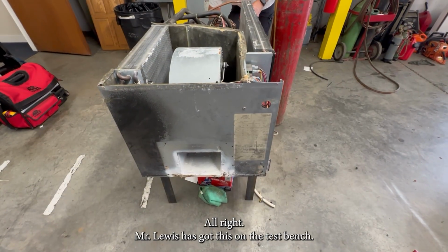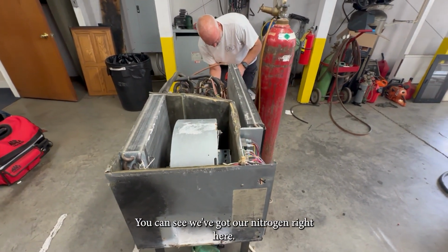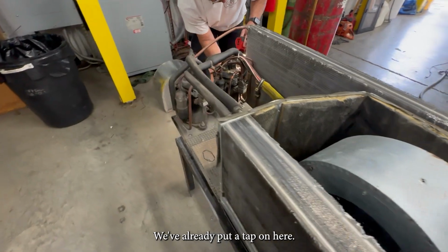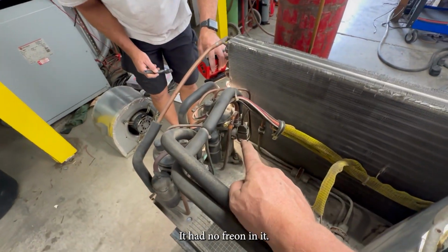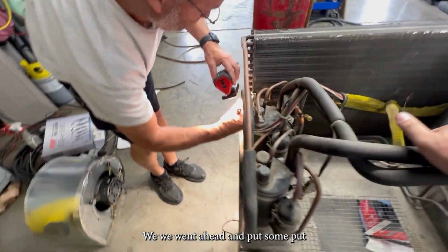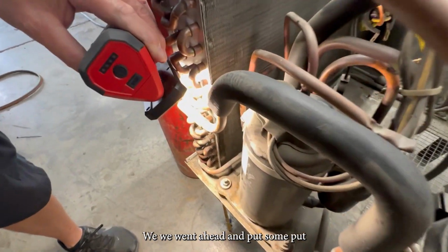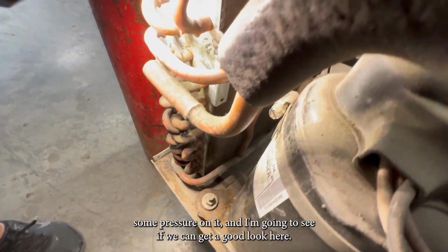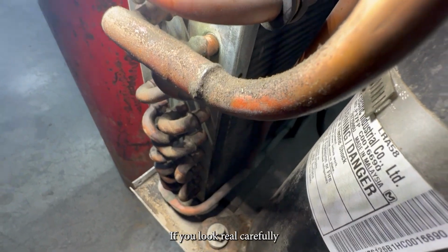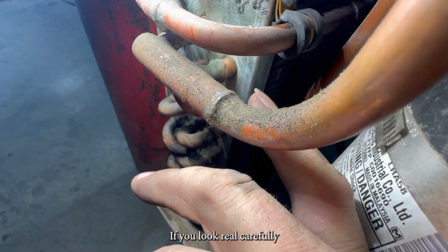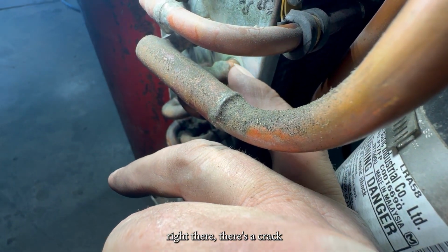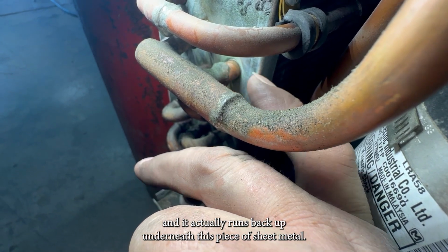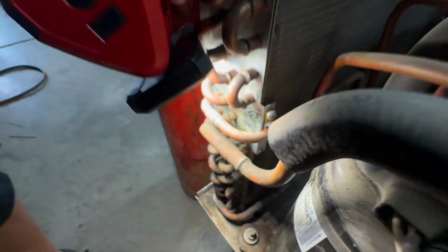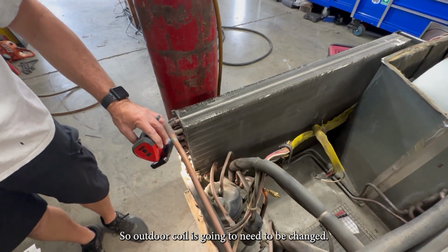All right, Mr. Lewis has got this on the test bench. You can see we've got our nitrogen right here. We've already put a tap on here. It had no Freon in it. We went ahead and put some pressure on it, and I'm going to see if we can get a good look here. If you look real carefully, right there's a crack, and it actually runs back up underneath this piece of sheet metal. So the outdoor coil is going to need to be changed.